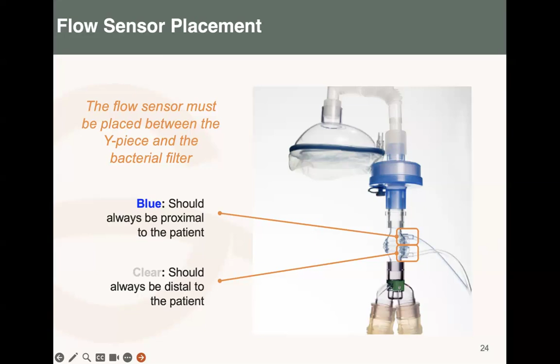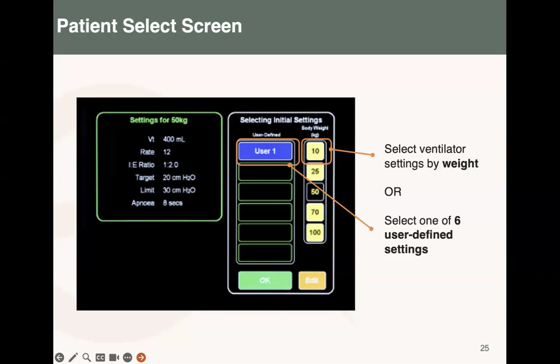Okay, so when switching on, the most important thing is selecting the patient, and there are two options. Either you go with the preset ones, which are done by weight, where you just pick the weight, and then the machine will display some settings, as shown on the left side. For example, now they just picked 50 kg, and these are some settings which have been displayed. Tidal volume is 400, rate is 12, the I:E ratio is there, and the limits are even shown, everything is displayed. The other way is the user ones, whereby you are the user, and you save them in the machine. As you see there, the user one can be, depending on your name, maybe Amis one, Richard two, whatever, and so when you come in, you just pick whatever you want, then that will take you to the machine and you continue with the machine. Next.